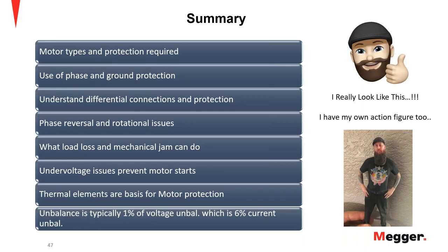Phase and ground overloads and short circuits can produce high fault currents, and it is very important to protect personnel first, and second, the equipment against these types of faults. These schemes have been working for over 75 years, and this allows the motor not to get into an overload situation when loads change or internal or external faults happen.